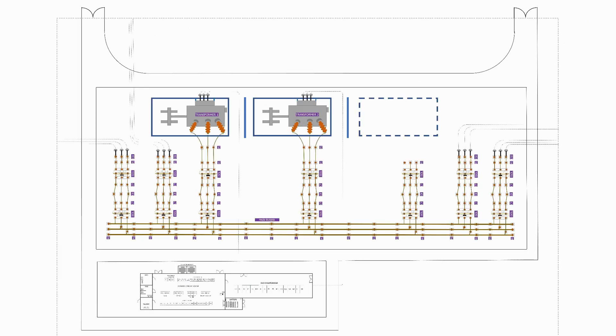Where do we measure the soil resistivity? Well, here's our typical 115 KV substation. As we've said previously, the soil will not be homogeneous and may vary considerably as we go across the site. So the best way forward is to take several measurements across the site and at different depths, so we can develop a good picture of what is going on with the soil.